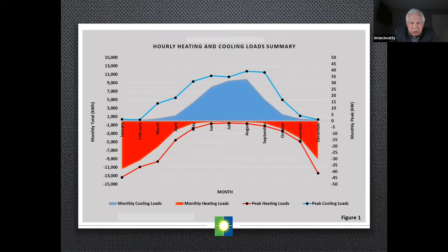Continuing with the design, once we have the loads, then you look at the details of the heat pumps. Every heat pump is manufactured a little differently. They perform differently. They use different temperatures and so on. And you have to understand the operating temperatures and the flow for geothermal. The flow meaning what flow are you putting down those loops in the ground, or what flow are you pulling out of the wells? So you have to understand flow and temperature.